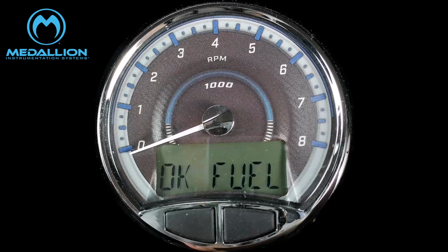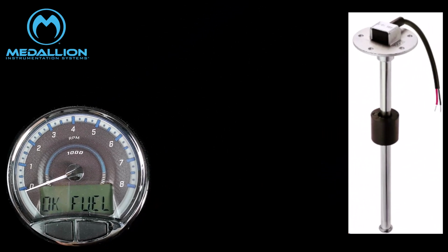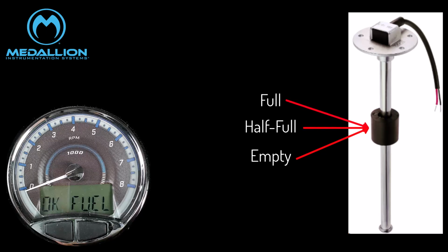It is a common mistake for people to calibrate this incorrectly. They will calibrate the empty, half full, and full position without adjusting the actual level in the tank. When they do this, they are actually telling the gauge that these 3 points of reference are identical. This will cause the needle for the fuel level to act erratically because, as the fuel level changes, the gauge can't determine where the true level is set because it thinks that all points of reference are equal.